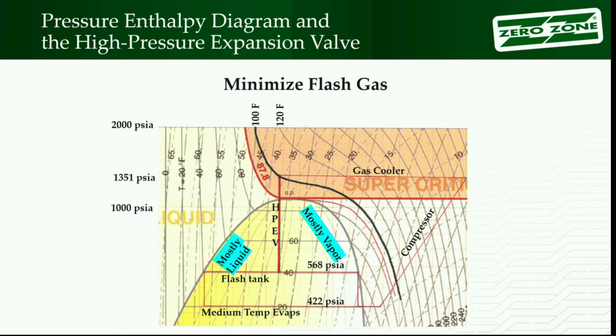But anyhow, this is a simplified version. I only showed the top half. So I drew in a heavy black line, 100 degrees. And I said, all right, it's 90 degrees outside. I'm only going to get this cooled to 100. So no matter what I do with my high pressure expansion valve, if I open the valve and drop the pressure, open valve lets more of it flow through, or if I close the valve and hold the pressure back at a higher pressure, in this simplistic world nothing's going to change. That temperature's still going to be 100 degrees. So no matter what I do with the valve control, with the pressure, I'm going to be riding along that line. That's the point I'm going to start with.